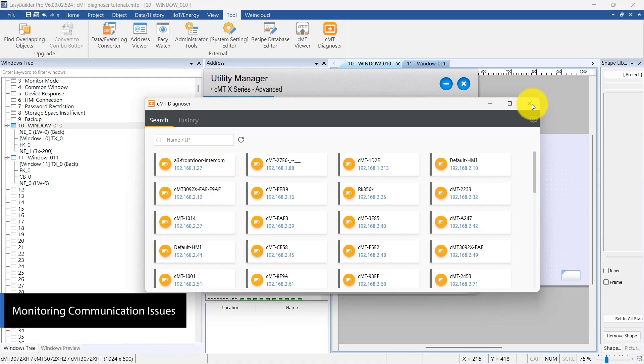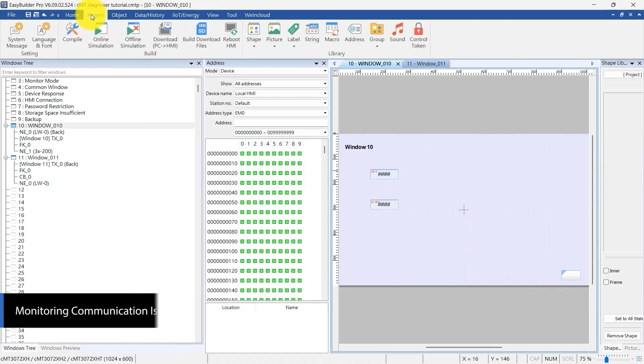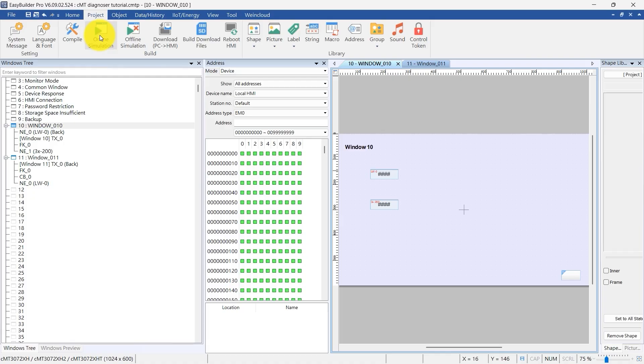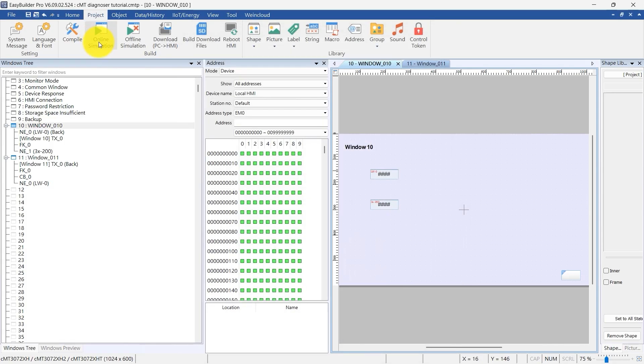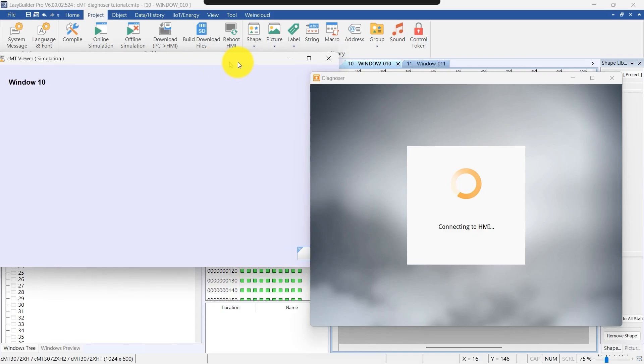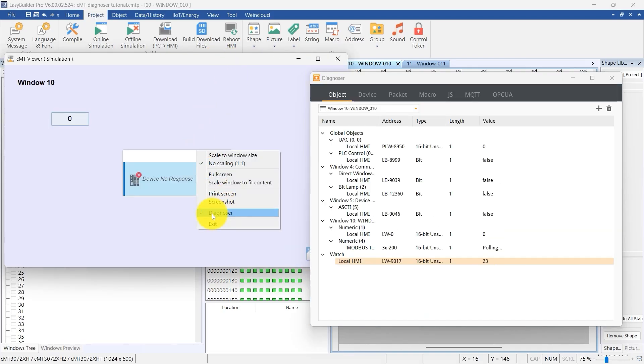Today, we will demonstrate the CMT Diagnoser using online simulation. First, a numeric object with the address 3x200, which does not exist on the device, will be placed on the screen. Using the Diagnoser, it is clear that this address cannot communicate and is stuck in a polling state.